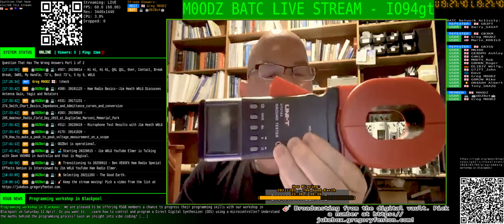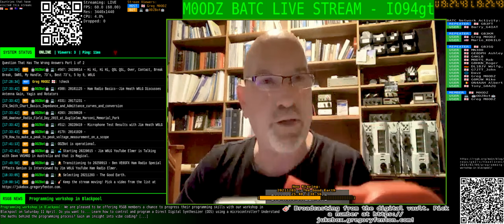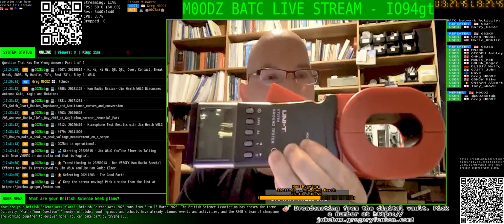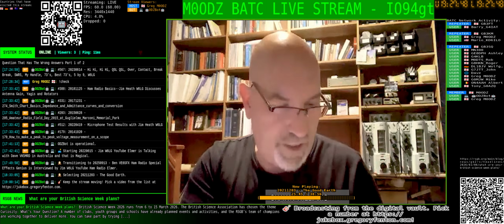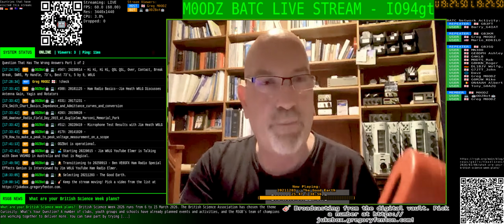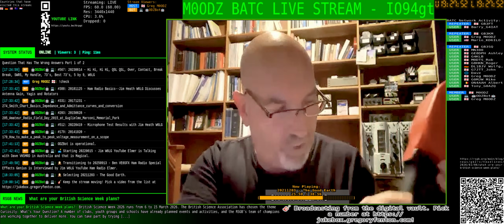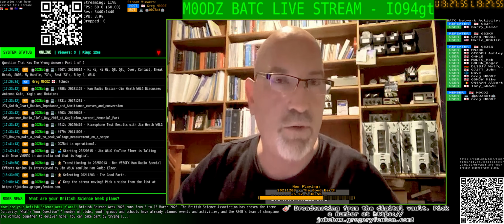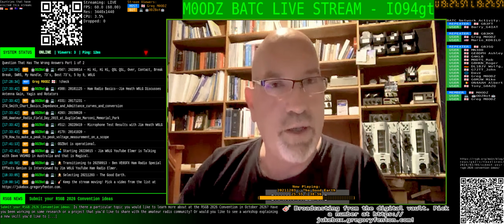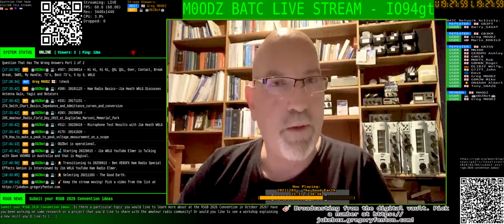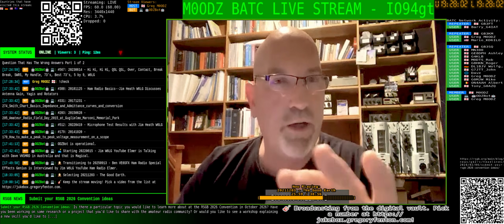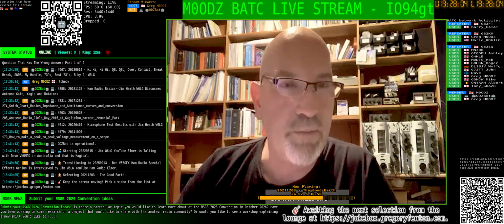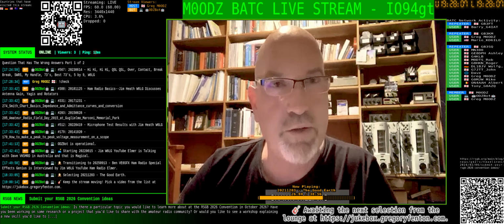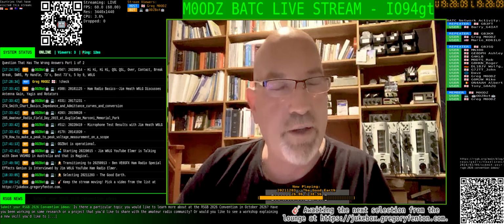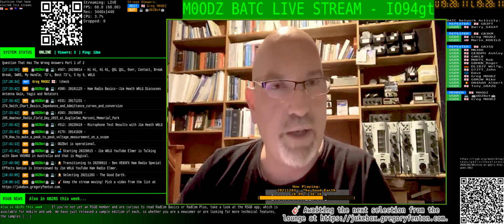Well, I have one of these in my station as part of the station equipment - there are different ones. This is a Uni-T, and you clip it around the ground rod and it gives you the resistance of the rod. So do you drive another rod into the ground somewhere, or do you just clamp it on? No, you connect the rod to your electrical system and couple it around the conductor that goes to the rod, and it calculates using high frequency pulses.